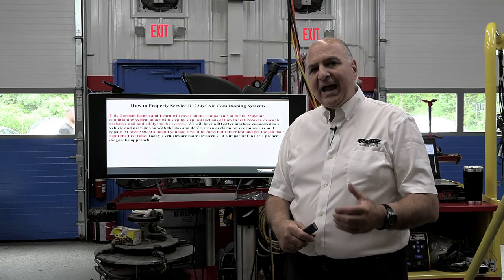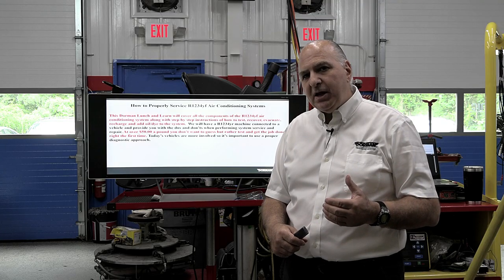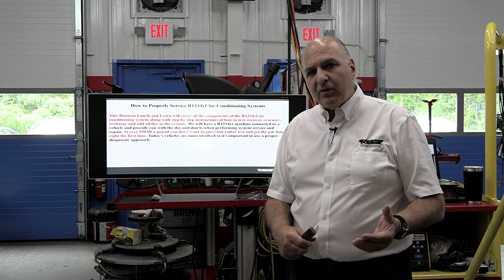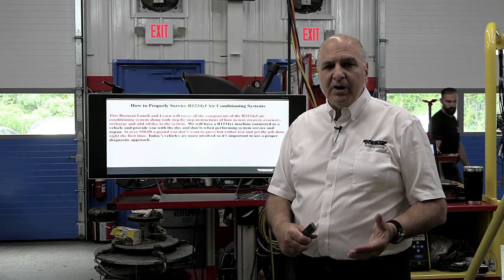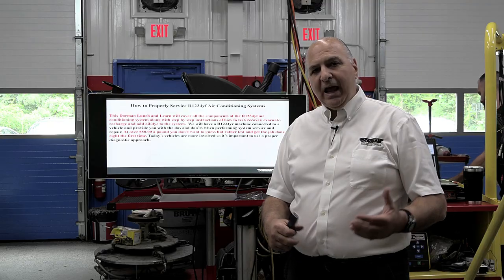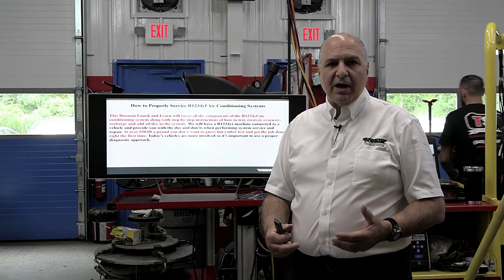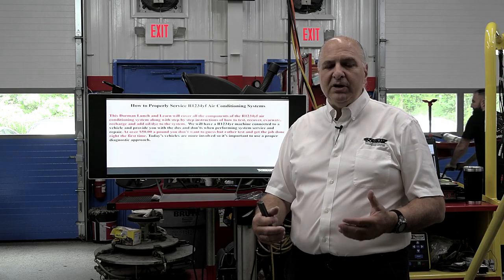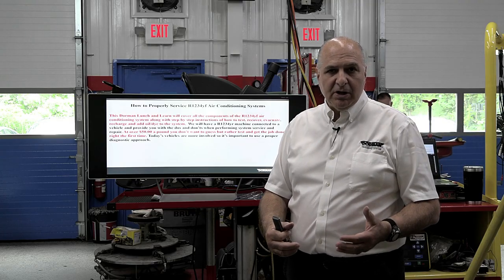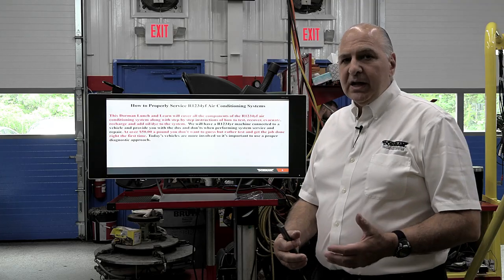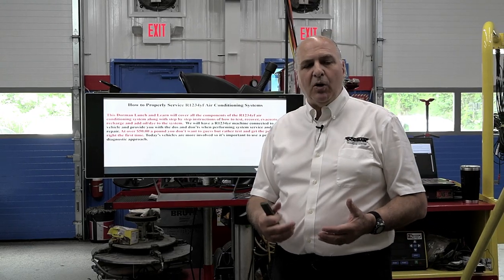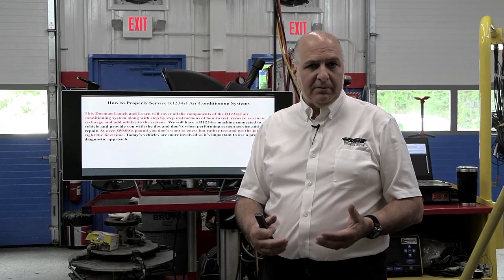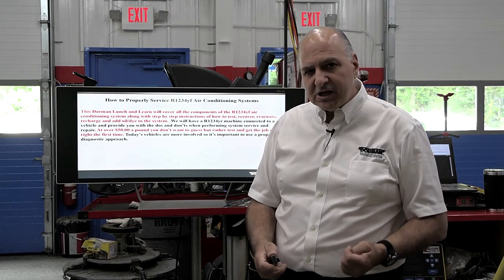But if you're just adding oil because maybe it blew some out, or you had a leaky Schrader valve, you'll add a universal POE oil, and you never go over 2 ounces. Usually what we use here is a hybrid electric POE that has dye in it, so if there's a leak, you can see it.